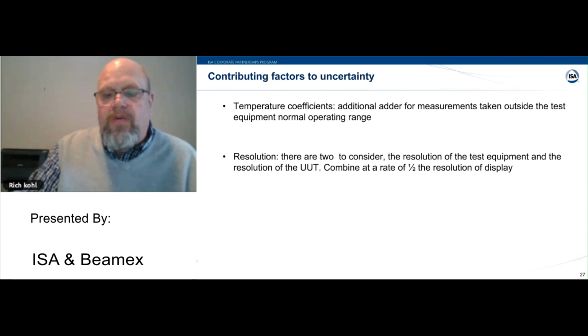So how do you know that you are within that range when you're actually making your measurement? Well, what you have to do is actually whip out your thermometer and take a measurement of the ambient temperature. Now, you saw in Roy's demo, one of the things he had to do in his automated calibration was enter temperature and relative humidity. So that's what that was for, this whole temperature coefficient thing. If it's within the operating range, you don't have any adders.